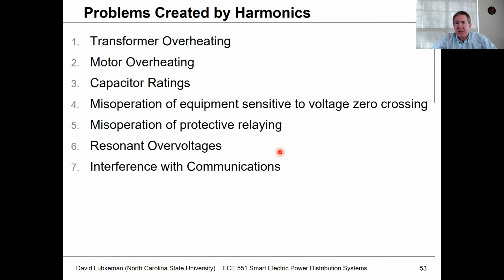And then if you have equipment that's sensitive to a zero crossing of the voltage, some older pieces of equipment would actually get a synchronization from the voltage crossing. This can cause certain types of equipment to misoperate. This could confuse, like, protective relays. If we had a lot of harmonic content, you would sometimes get what we call resonant overvoltages, and we'll get into that in just a little bit. And this could also interfere with communications. If you have harmonics flowing in the line, especially the higher order harmonics, and you have a nearby phone cable, let's say, then this noise can get induced into the phone cable and can actually interfere with communications.